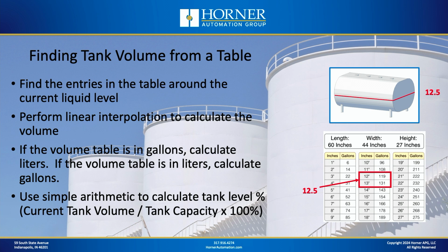Okay, and then you would need to find on the chart the closest entries that are around your current fill level. Once you've done that, you would take the data from those entries and perform linear interpolation to find the closest estimation of volume based on your level.